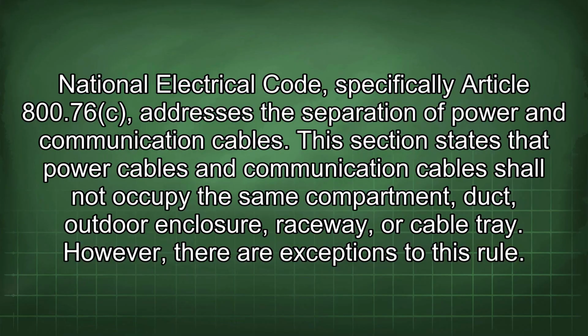National Electrical Code, specifically Article 800.76, addresses the separation of power and communication cables. This section states that power cables and communication cables shall not occupy the same compartment, duct, outdoor enclosure, raceway, or cable tray. However, there are exceptions to this rule.